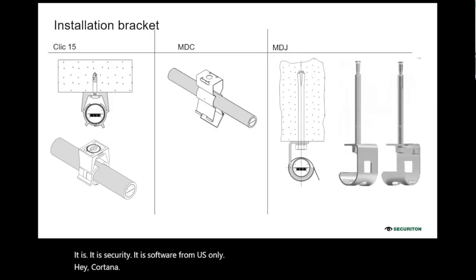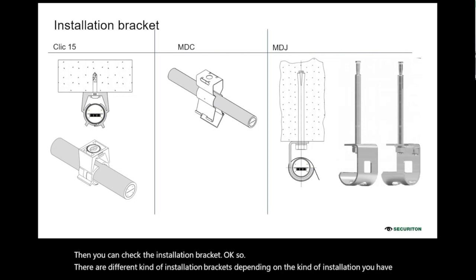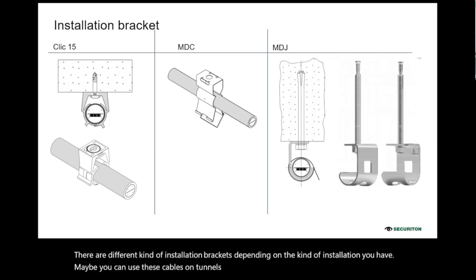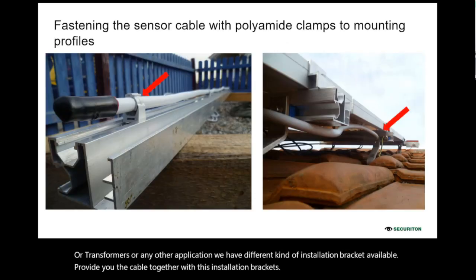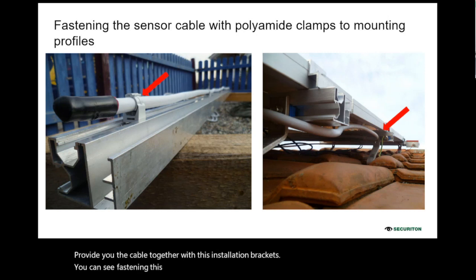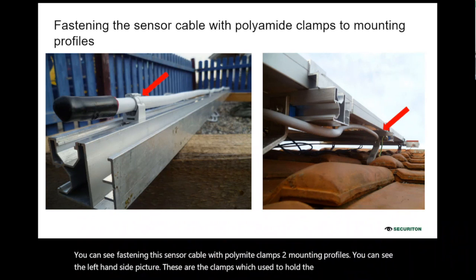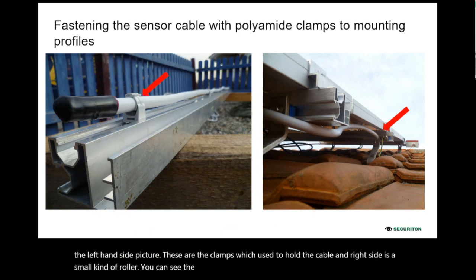Then you can check the installation bracket. There are different kinds of installation brackets depending on the kind of installation you have. Maybe you can use these cables in tunnels, on conveyor belts, on transformers, or in any other application. We provide you the cable together with these installation brackets. You can see the sensor cable being fastened with polyamide clamps to mounting profiles. On the left-hand side picture, these are the clamps used to hold the cable, and on the right side is a small roller. You can see the different kinds of mounting profile or clamp.